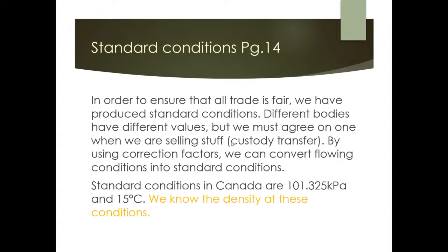Different correction factors are used to convert flowing conditions into standard conditions. In Canada, standard conditions are 101.325 kPa and 15°C. The reason these standards matter: knowing the medium, pressure, and temperature allows us to determine density, which allows us to sell a specific mass of product — like the chip bag analogy: large volume, known quantity of chips inside.